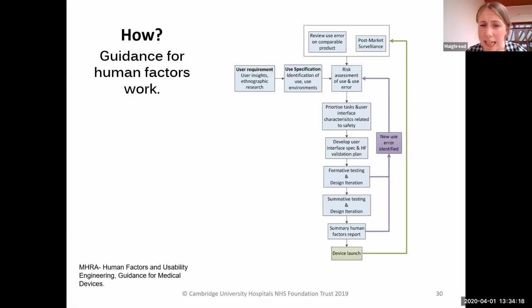And you can then do an assessment on your user, maybe using a prototype or maybe having a volunteer using it before your user themselves actually comes into contact with it. And you then do some testing, so looking at formative testing, and out of that formative testing, you can then iterate your design. And this then starts to go into a continuous loop for users.